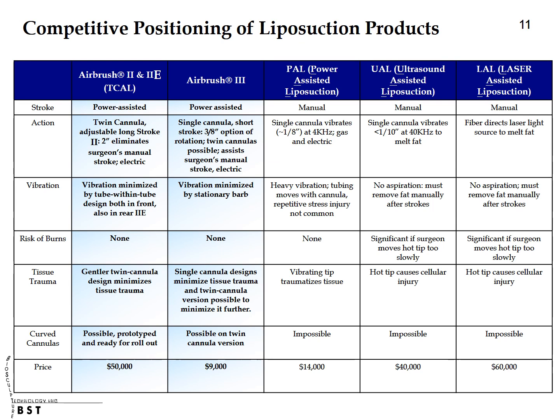Airbrush 3 targets the microwear PAL device in the middle, which has to be replaced every few years because of cumulative autoclaving wear. We plan to price Airbrush 3 approximately one-third cheaper with a projected 83% margin. Airbrush 3's stationary barb design is subject to less vibration, a problem doctors complain of with the PAL device. Airbrush 2E on the left has a mechanical advantage superior to the hot poker tips posed by the ultrasound or laser devices on the right in treating fibrous areas and is at a similar price point to the ultrasound units. But our unit can't cause burns as the tips remain cool, and it is faster and less bloody. Further, it eliminates the need for the surgeon to stroke the device back and forth, eliminating the work from the procedure.